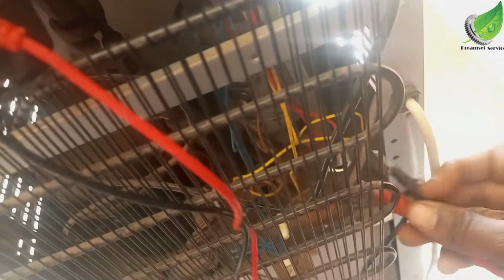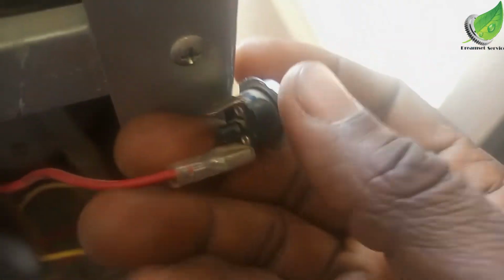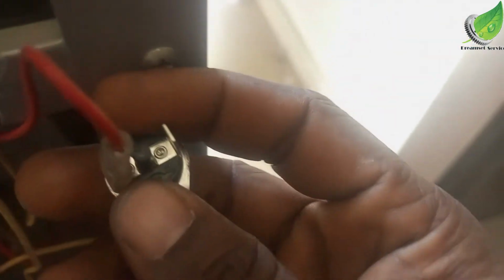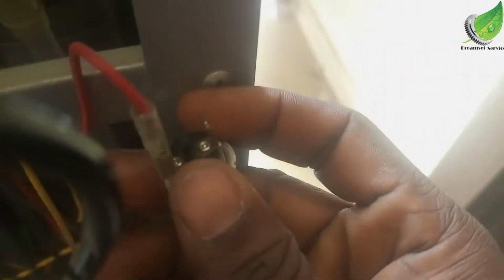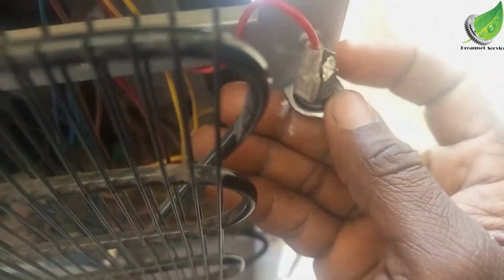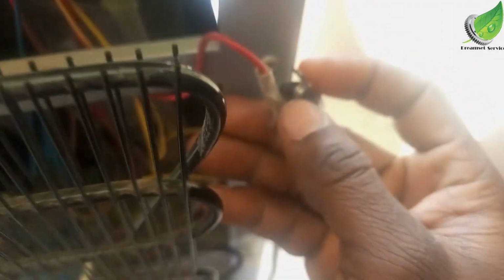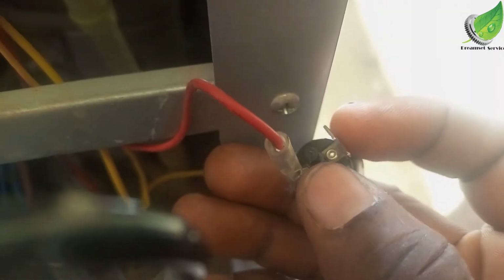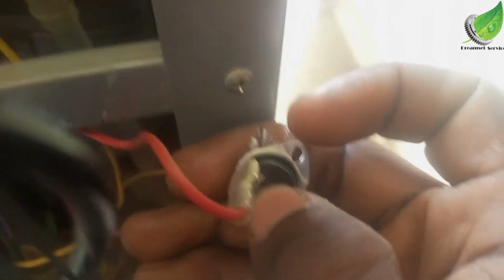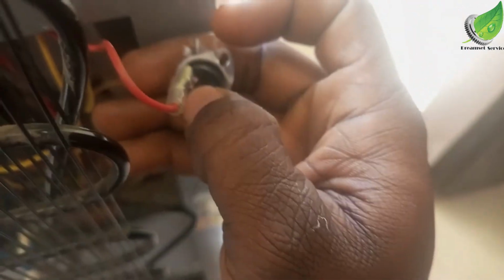Alright, I'm going to test again. You can see it's not reading at all, there's no continuity between the two legs, which is bad. So what you do when you have issues like this is recalibrate it, because this sensor shuts itself off if it notices any danger or unusual heat in the hot water area.